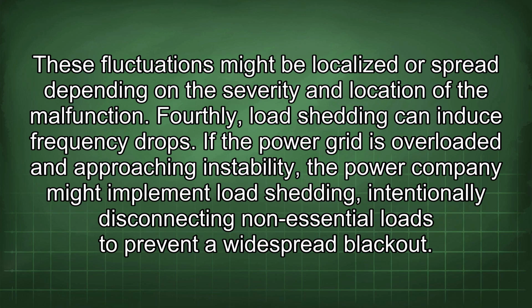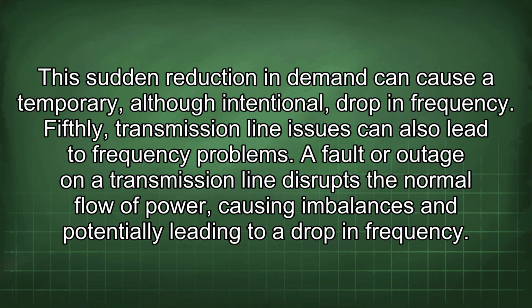Fourthly, load shedding can induce frequency drops. If the power grid is overloaded and approaching instability, the power company might implement load shedding, intentionally disconnecting non-essential loads to prevent a widespread blackout. This sudden reduction in demand can cause a temporary, although intentional, drop in frequency. Fifthly, transmission line issues can also lead to frequency problems. A fault or outage on a transmission line disrupts the normal flow of power, causing imbalances and potentially leading to a drop in frequency.